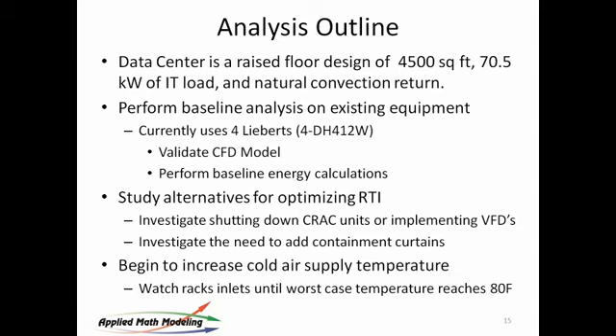And the data center we're going to be looking at today is a standard 4,500 square foot raised floor data center. It uses natural convective return. It's got about 70 kilowatts of IT load. They're using 4 Lieberts in it. And the process we'll use is to validate the model, perform baseline energy calculations, and then begin to modify by first going for RTI, trying to get the air in place. And then we're going to use some containment to optimize the airflow. And then we're going to be able to walk up the cold air supply temp and see how far we can get.